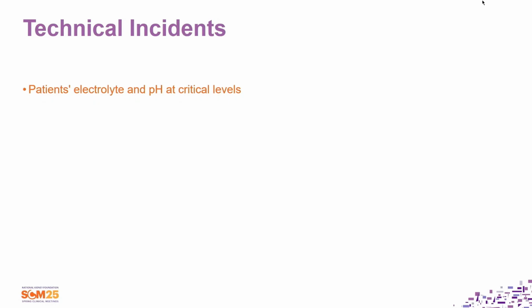For example, sodium: measured dialysis delivered sodium versus prescribed sodium. As you say, there's the manufacturer of the concentrate, with a plus or minus allowance, I think it's like 2.5. But then the machine has a plus or minus allowance too. So when you start adding all those plus and minuses, we look at our dialysis and it was plus or minus 10 of what you think.